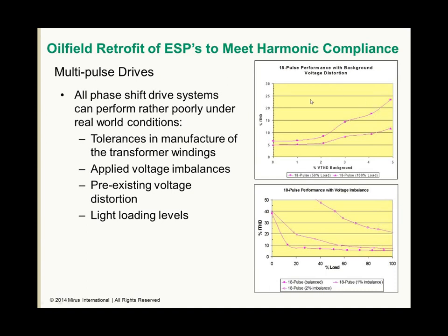The two charts on the side of this slide show 18 pulse VFD's performance with background voltage distortion, going from no voltage distortion all the way up to 5% voltage distortion. And we show the VFD's performance at full load and at 50% load. And we can see how the current distortion increases dramatically as we increase the voltage distortion applied to the drives.